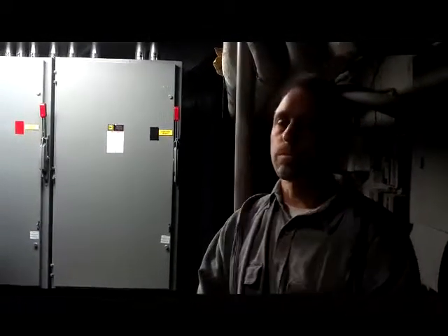So they were spending 60% more than they should, from 60 to 96 is 60% more, and we reduced it 40%, and they like their system. The cycling count went down, so we're not cycling the boilers as much. That control is basically got some intelligence. And once we set this control up, it's not a walk-away control like we did with the boilers. They walked away, they had to come back and make it work, but it's because of the piping and how it's laid out, it wasn't the most ideal system. But they got it to work, but we're going to improve it even more.